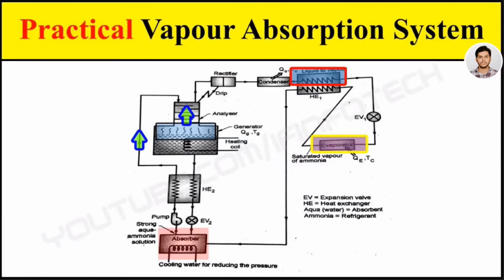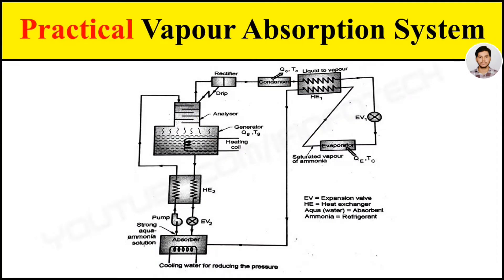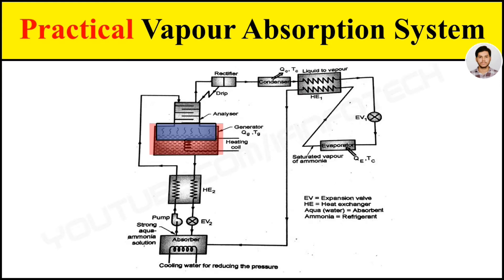Hello everyone. In this video I will show you the working of a practical vapor absorption system, fitted with an analyzer, rectifier, and two heat exchangers. The vapor rises from a strong aqua ammonia solution in the generator where heat is supplied externally. This vapor consists of ammonia vapor with a small quantity of water vapor.